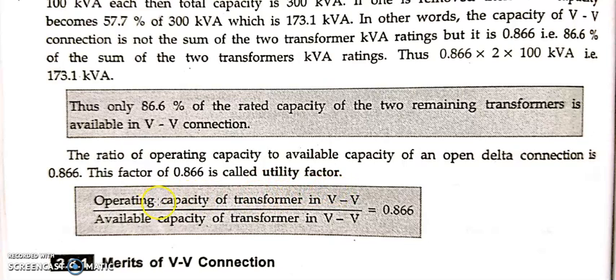It is defined as the ratio of the operating capacity of the transformer in VV connection divided by the available capacity of the transformer in VV. So we know that the operating capacity of the transformer is around 57.7%, yes or not? And again the available capacity is how much? Totally 2 transformers means it is 66.67%, yes or not? So 57.7% divided by 66.67% would result in 86.6% or 0.866. Okay.